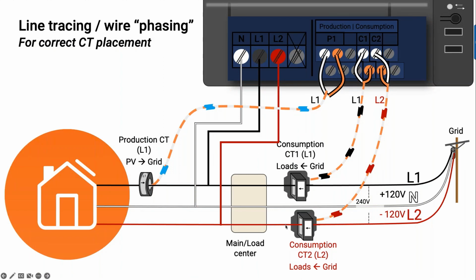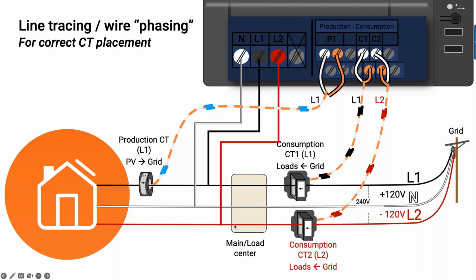So for example, if you've got a line 1 voltage and it's actually coming through your load center and it actually gets crossed, right? You probably see my arrow here. Then what happens is that this line, which I'm getting a voltage measurement from, which is line 2, if this line coming from the utility is crossed through the load center, then this is actually line 1 where we think it's line 2. So you can see the problem: I'm measuring current from line 1, but as the voltage goes through my load center, I'm actually measuring voltage from line 2, right? Because it's crossed through here.